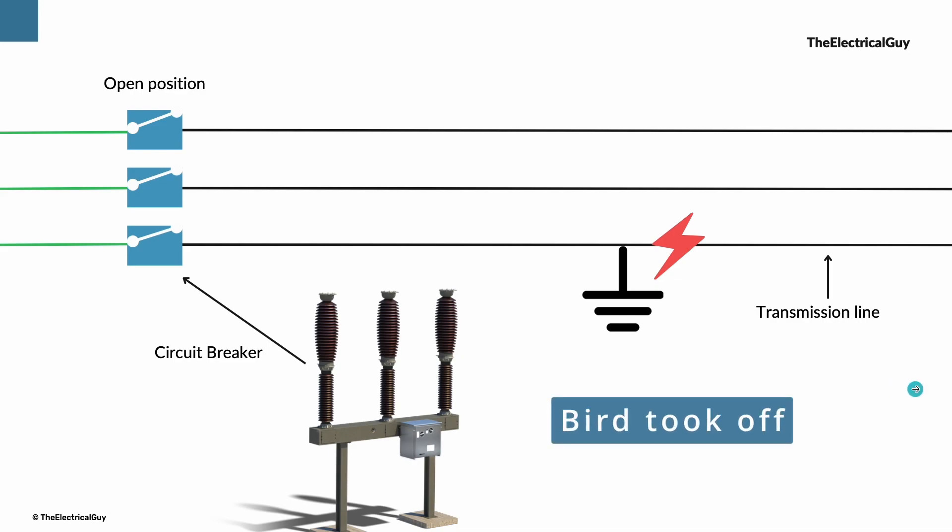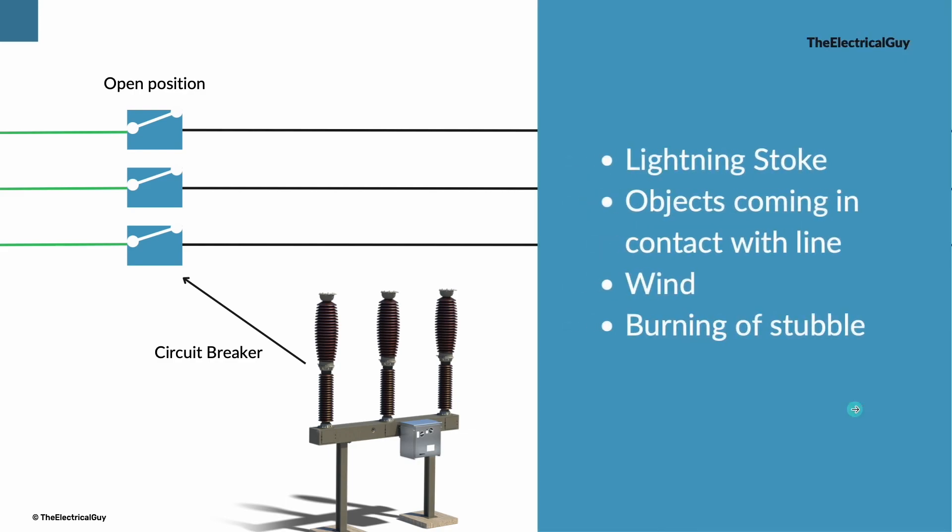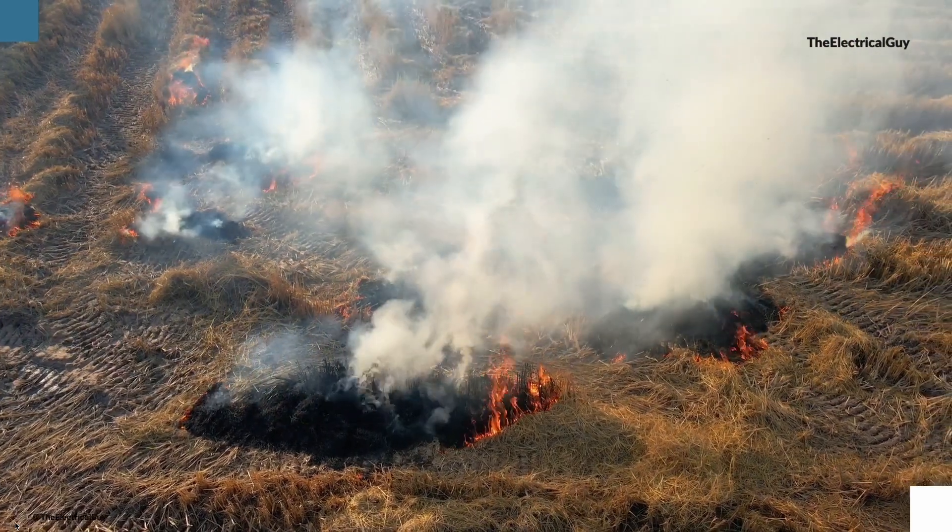Once the bird took off, the fault will clear quickly, but unless the operator operates the breaker, the supply will not be restored. Now I gave you example of bird crashing, but there can be other causes of fault like lightning strike or some objects coming in contact with the line, wind causing jumper loops to flash over to the tower legs, or maybe farmers burning stubble in their field.